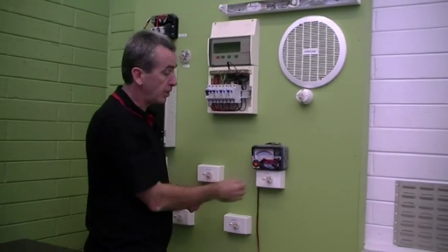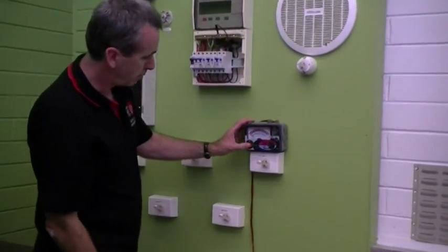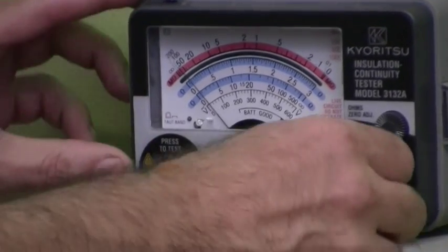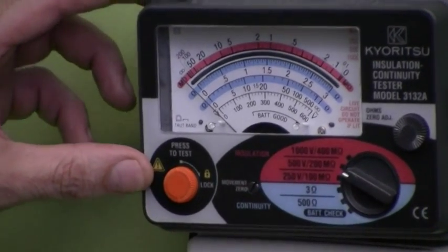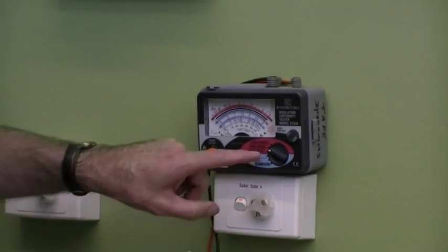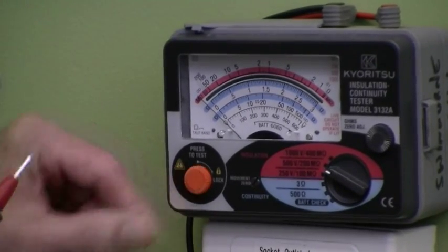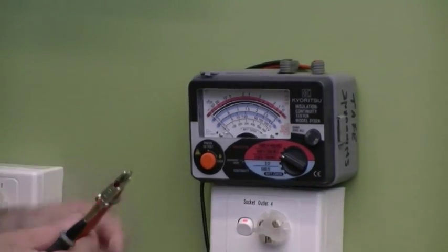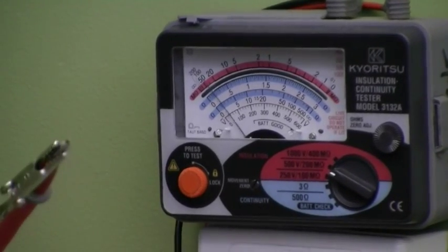I've got the Megger here and I've got to make sure it's in working order. I'm putting the left switch to battery check — push the button and make sure the battery's in good condition. That looks fine. I'll go to the 500 volt scale we're going to use and make sure the meter's reading accurately. With the leads apart on 500 volts, reading the outside pink scale, it should read infinity mega ohms — and sure enough the pointer stays at infinity. Shorting the leads together, it should read zero mega ohms — and it does. The meter is now confirmed in working order.